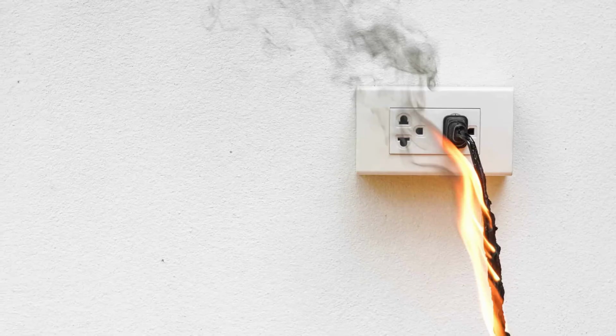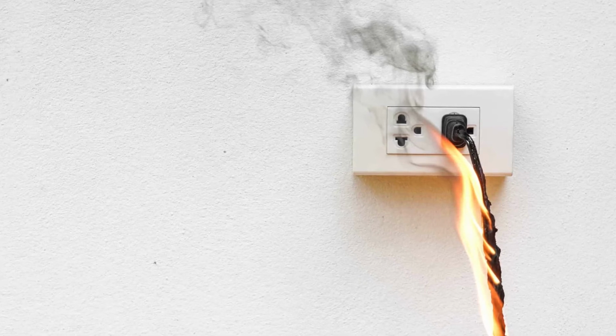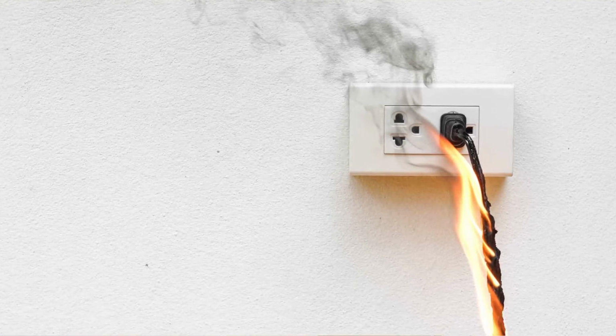How often have you found this? Many times. Very, very frequent. It could be due to somebody not connecting the earth wire there, or saving on the wires sometimes. Correct. So these things cause electrical shocks if the earthing is not okay. So all the 3 points are checked in this.